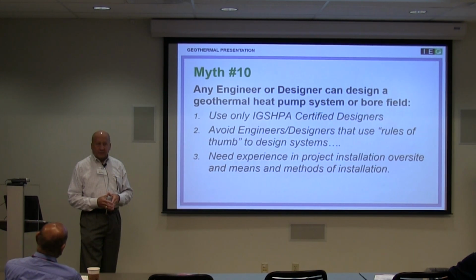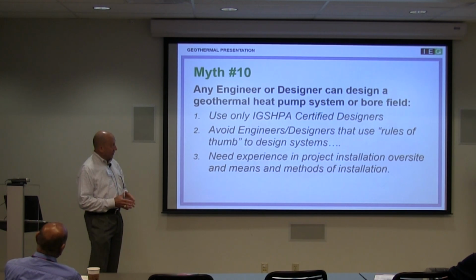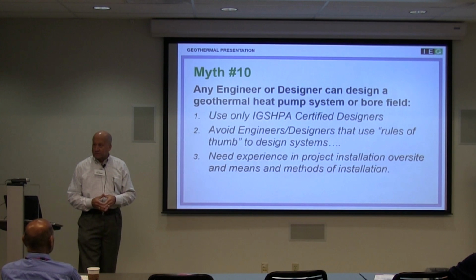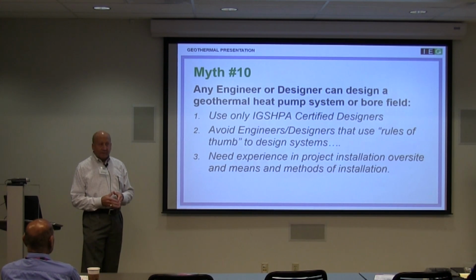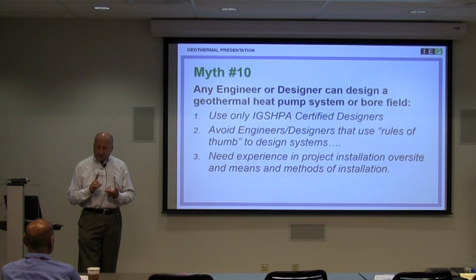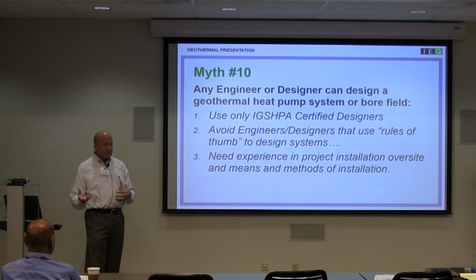These engineers need to go to those classes. They need to understand that it's not a condenser water system. There are other aspects of that design. You've got velocities you have to be very aware of, not just for operation, but for purging. When you're selecting that pipe size, you've got to know that you can maintain those velocities and achieve them to adequately purge it. It's not hard, to be honest with you.